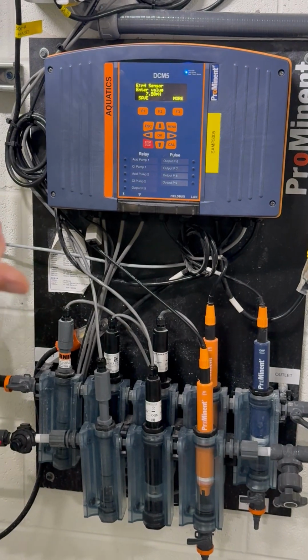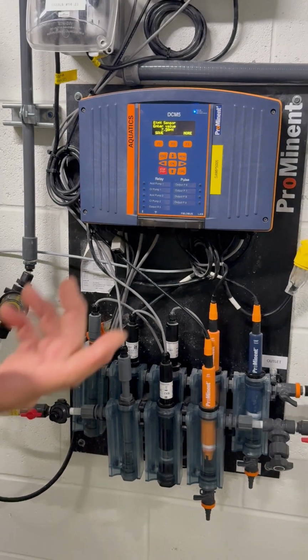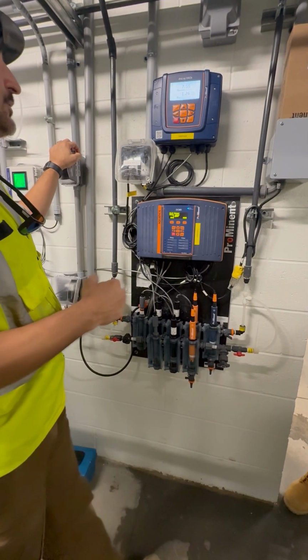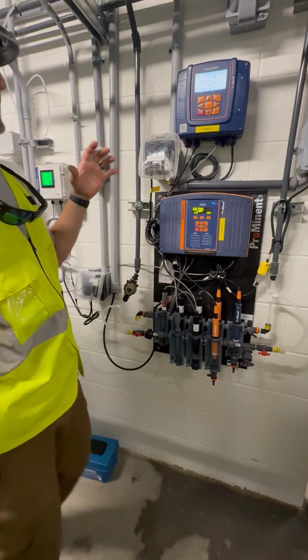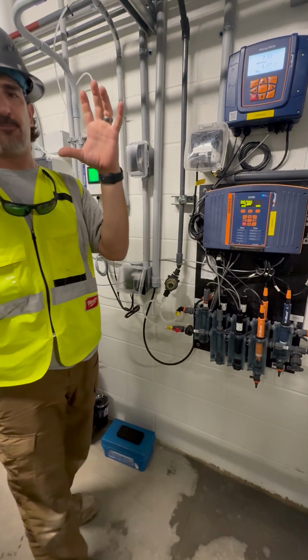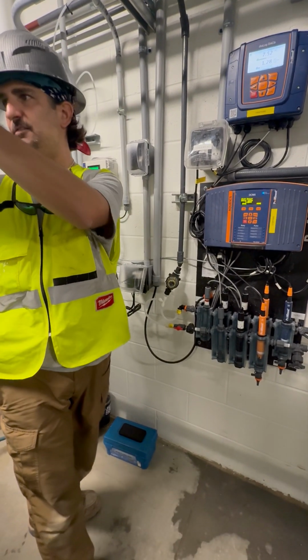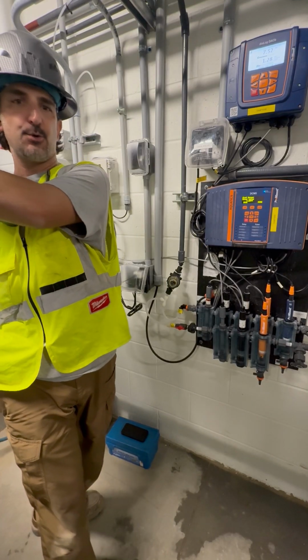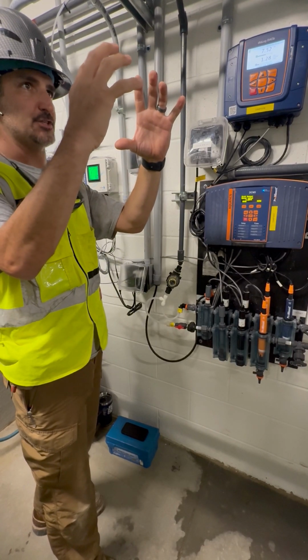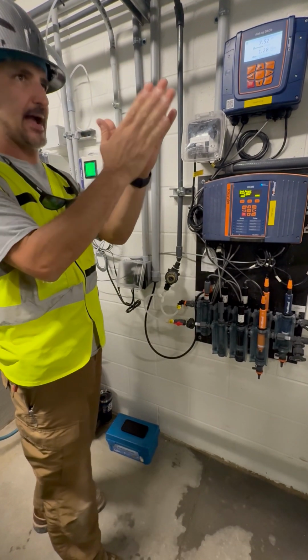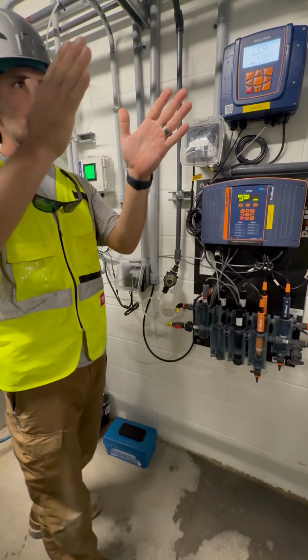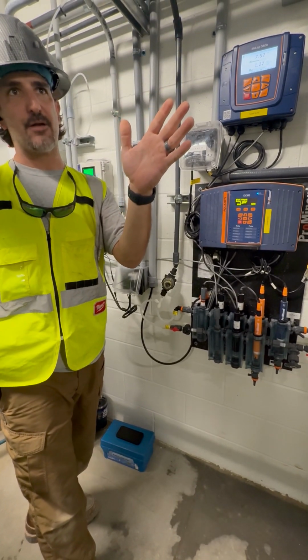Once you clean your probe, or once you get a new probe, you need to do a factory reset. When you factory reset, you're taking all that calibration - you went offset, offset, offset, offset. Factory reset brings it back to 0. So you take all that calibration out and move it back to the 0 point, and then we start getting farther and farther away as we calibrate farther and farther away.